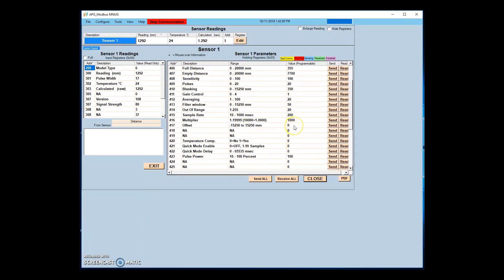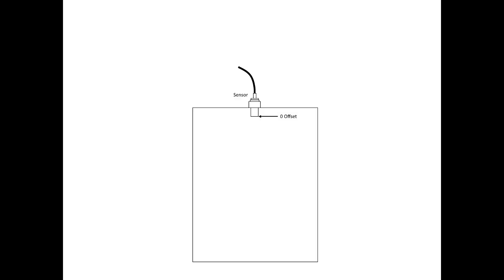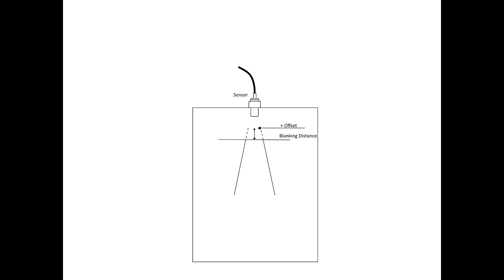Offset sets the point from which calculated distance will be measured. If the offset is set to zero, this point is the transducer face. Changing the offset positive moves the zero point away from the transducer and towards the target. Moving the offset negative moves the zero point behind the sensor face. Blanking is measured from the end of the offset.